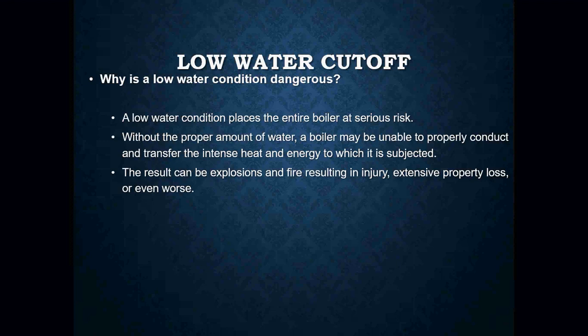A low water condition places the entire boiler at a very serious risk. Without the proper amount of water, a boiler may be unable to properly distribute and transfer the heat and energy that it's being subjected to. This can result in an explosion, fire, injury, extensive property loss — or even worse. Boilers can explode, especially if run completely dry. A hot cast iron boiler being introduced with cold 50-degree water is a ticking time bomb and can honestly explode or rupture and do serious damage to people around it.